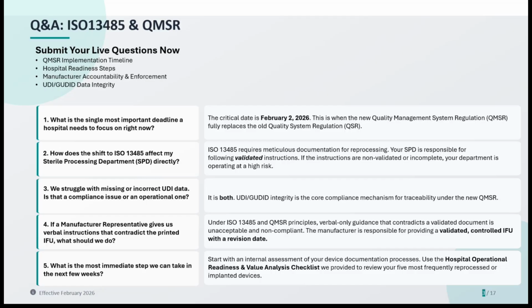Number four, if a manufacturer's representative gives us verbal instructions that contradict the printed IFU, what should you do? I had this happen today, actually. Under ISO 13485 and QMSR principles, verbal guidance that contradicts a validated document is unacceptable and non-compliant. The manufacturer is responsible for providing a validated, controlled IFU with a revision date. Your policy should be to reject verbal guidance and escalate documentation gaps immediately, as the device may not be safe or compliant to use. Only follow the manufacturer's controlled printed documentation, or you can actually view the PDF.